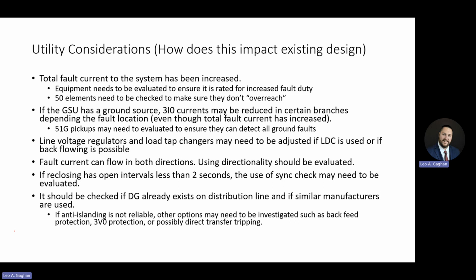Instantaneous overcurrent elements need to be checked to make sure that they don't overreach, right? If something was set to 5,000 amps, well, now we're having more than that. It may trip when we didn't previously intend it to. The GSU has a ground source. The 3I0 current may be reduced in certain branches depending on the fault location, even though the total fault current has increased. So the 51G pickups actually may need to be evaluated to assure sensitivity.